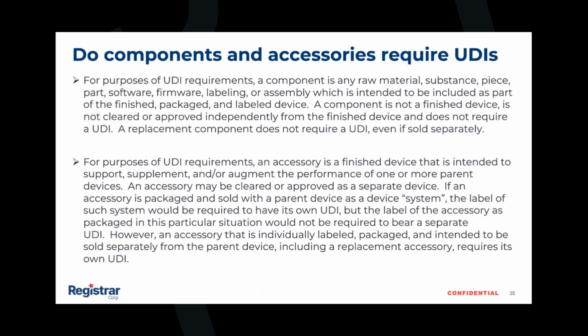On the other hand, an accessory is a finished device that is intended to support, supplement, or augment the performance of one or more parent devices. An accessory may be cleared or approved as a separate device, but keep in mind, if an accessory is packaged and sold with a parent device as a device system, the system label would be required to have its own UDI. But the label of the accessory as packaged in the particular situation would not be required to bear a separate UDI. If an accessory or replacement accessory is individually labeled, packaged, and or intended to be sold separately, it requires its own UDI.